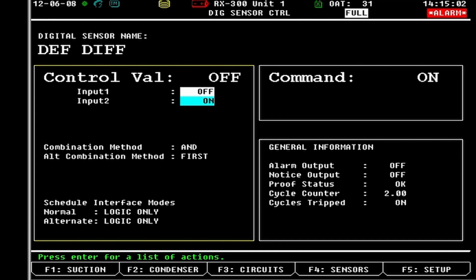compressor cycle counting. So in the E2, you only carry cycles for the day, for 24 hours. So you could set up digital logging to where it gives you longer, like a week or 2 weeks. I do a lot of stuff where I'll set up each individual compressor cycle counts in the controller, and I will count it and I will reset it every week, so that way I have a weekly cycle count, or a monthly cycle count of how many times we cycle things on and off. That's what I'll use digital sensor controls for.